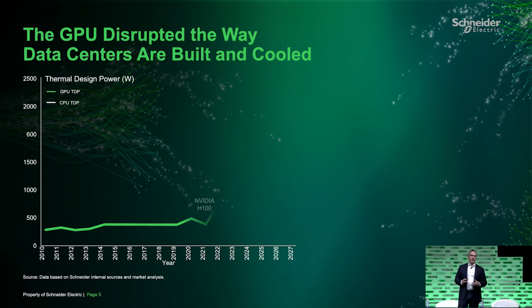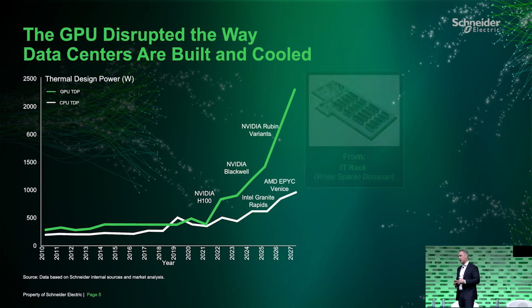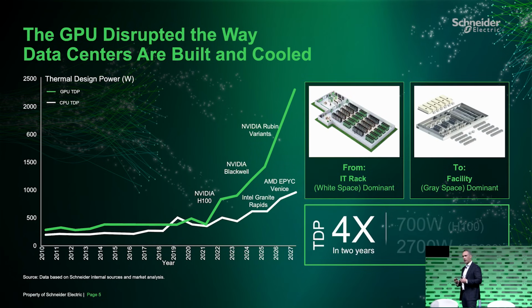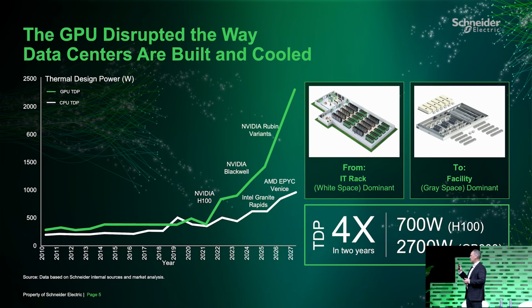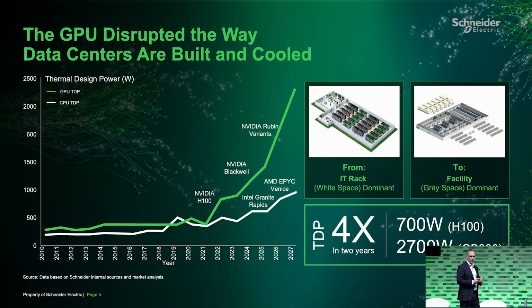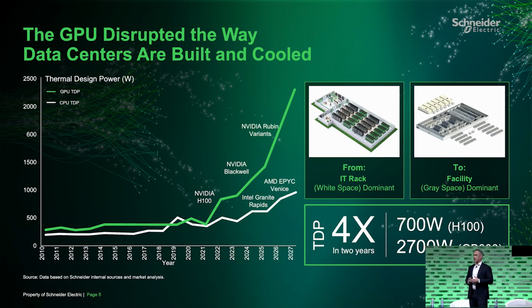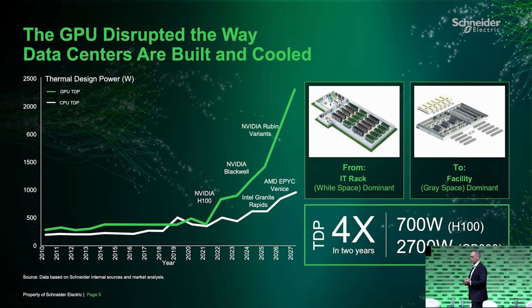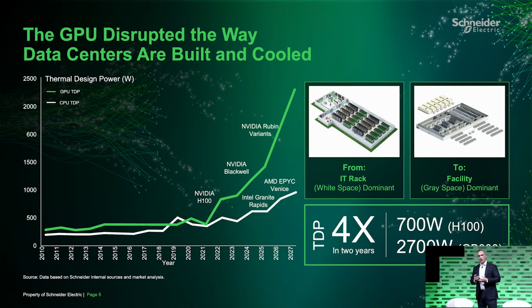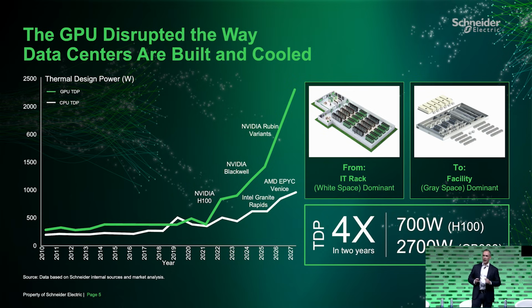To give you some perspective, we've been looking at this thermal challenge for many years at Motivair. In fact, I was reminded by a chart put together by ASHRAE, the ASHRAE TC 9.9 — American Society of Heating and Refrigeration Engineers — 6 or 7 years ago, where the whole industry got together: the leading silicon manufacturers, the leading server manufacturers, the leading hyperscalers making their own silicon in certain cases. They were trying to define where the industry was going without sharing their secrets.